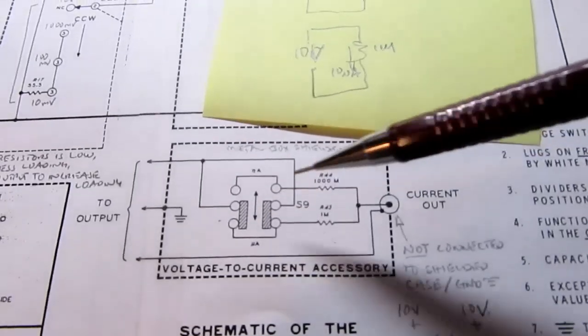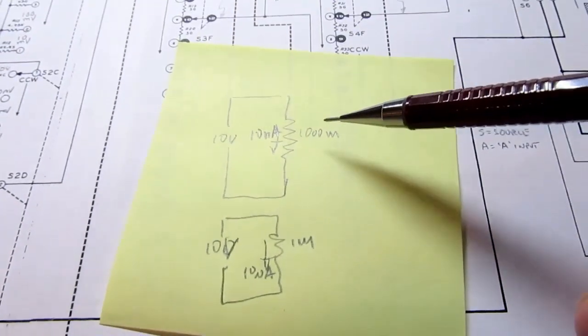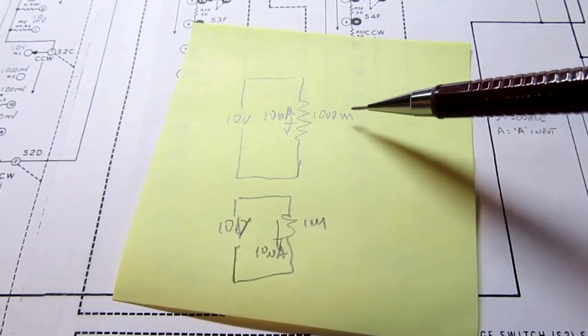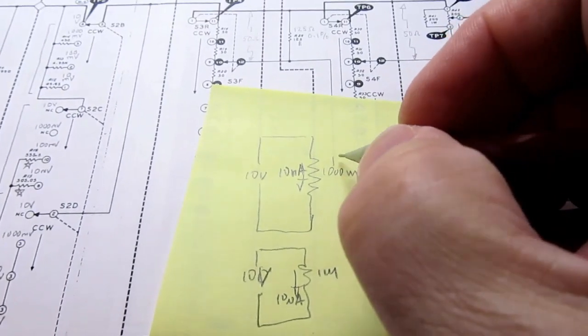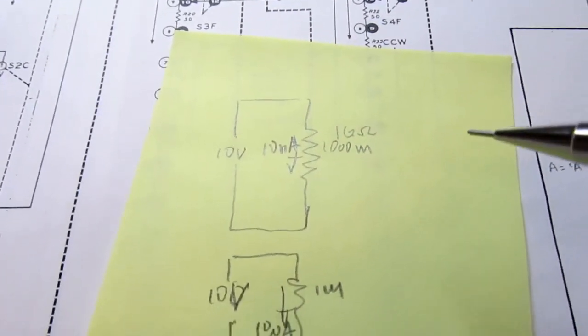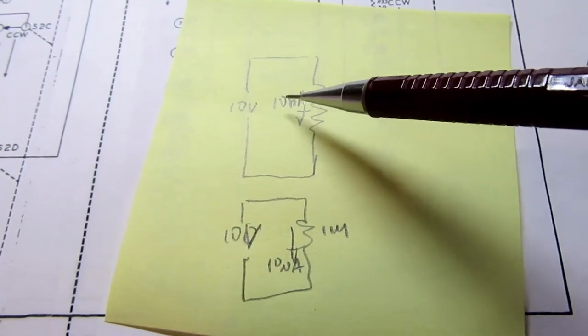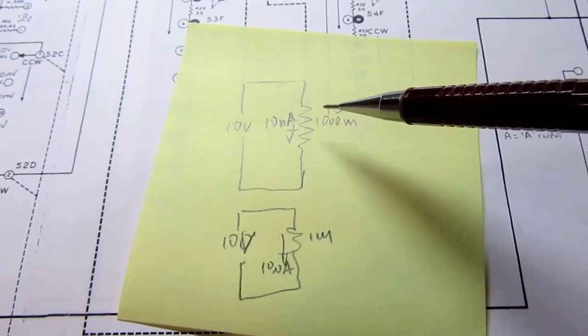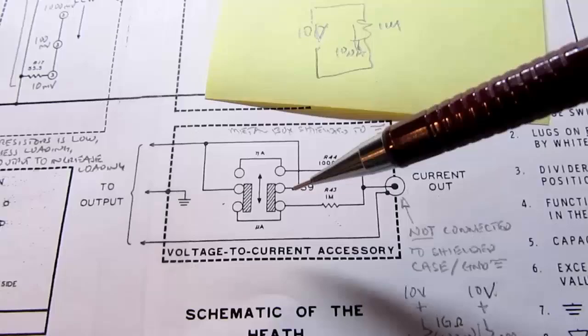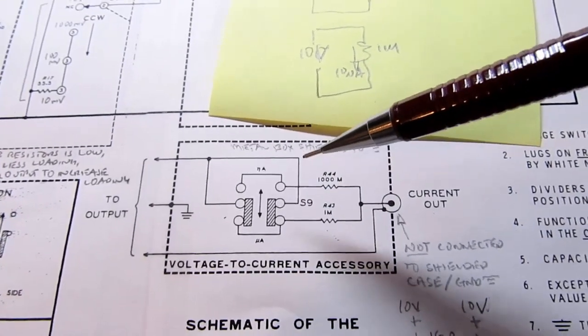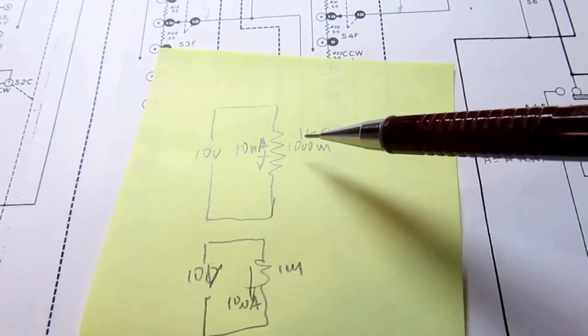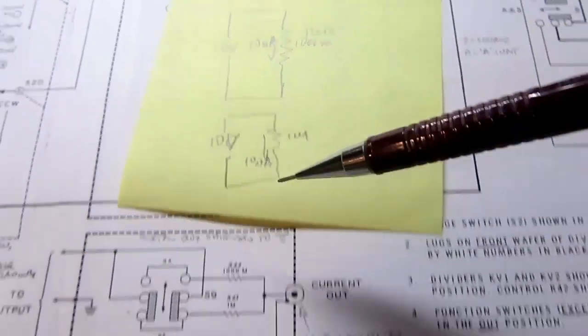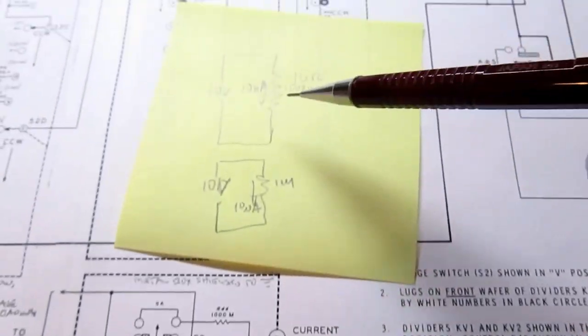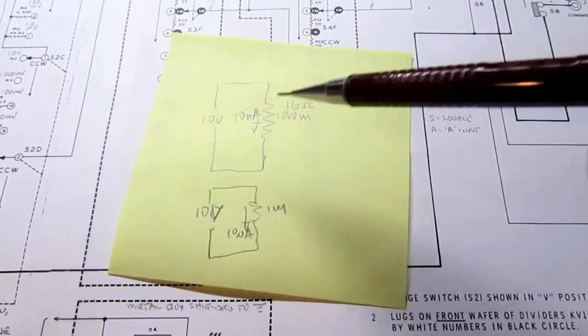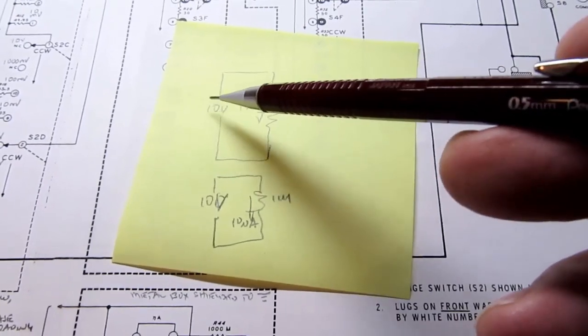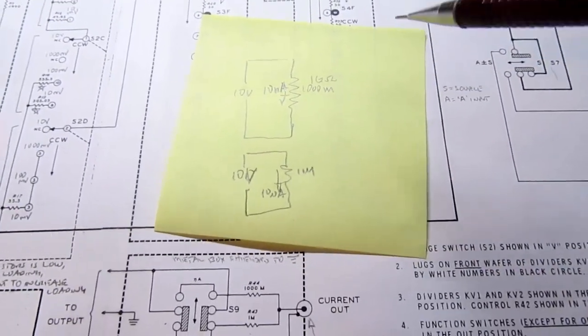If you have the switch here in the other position, now you're going up to 1000 mega ohms, which is 1 giga ohm. And you do the math, assuming 10 volts out here, and it comes out to 10 nanoamps. So again that's what this is supposed to do: it's either going to be a 10 microamp or a 10 nanoamp output current. And once again, because this is such a huge resistance, it doesn't really matter what else you put out here. It's going to be tiny compared to this, so you're getting 10 nanoamps or whatever lower value you set by lowering the voltage here.